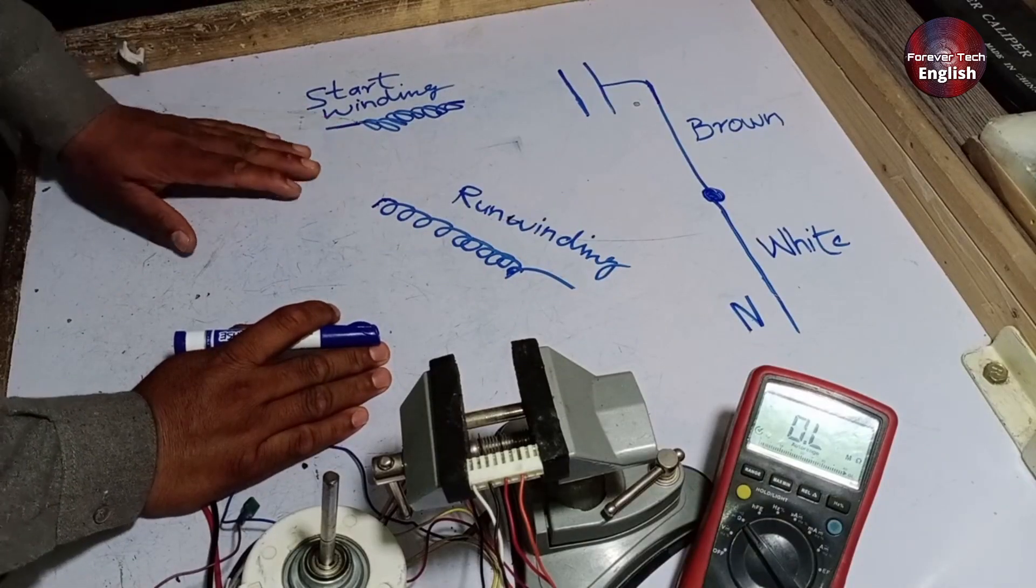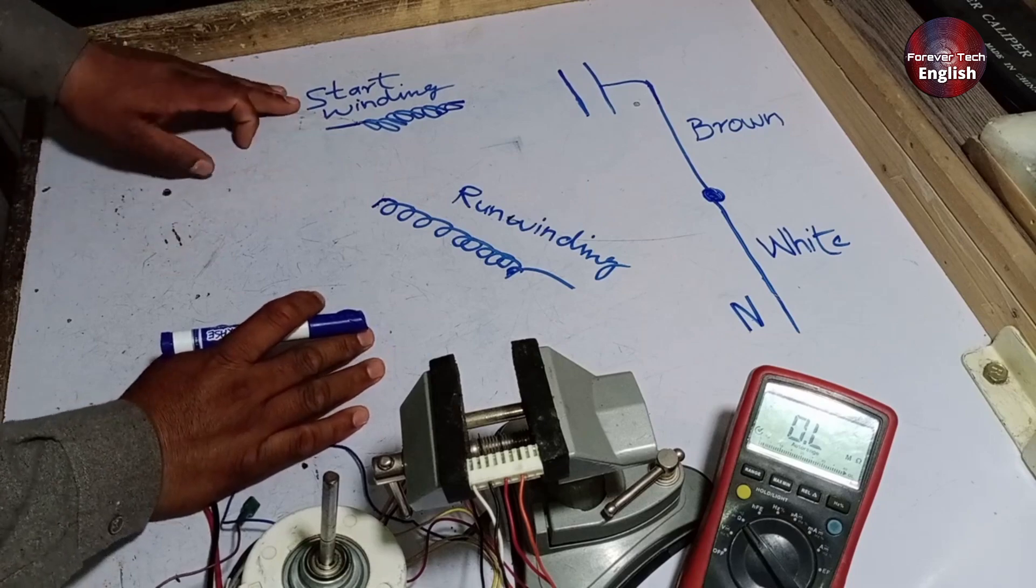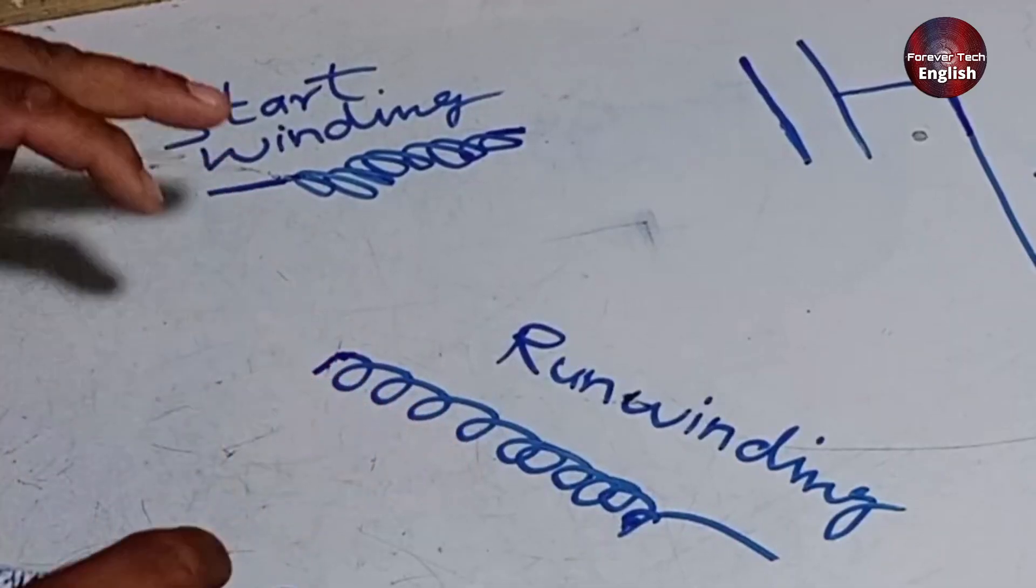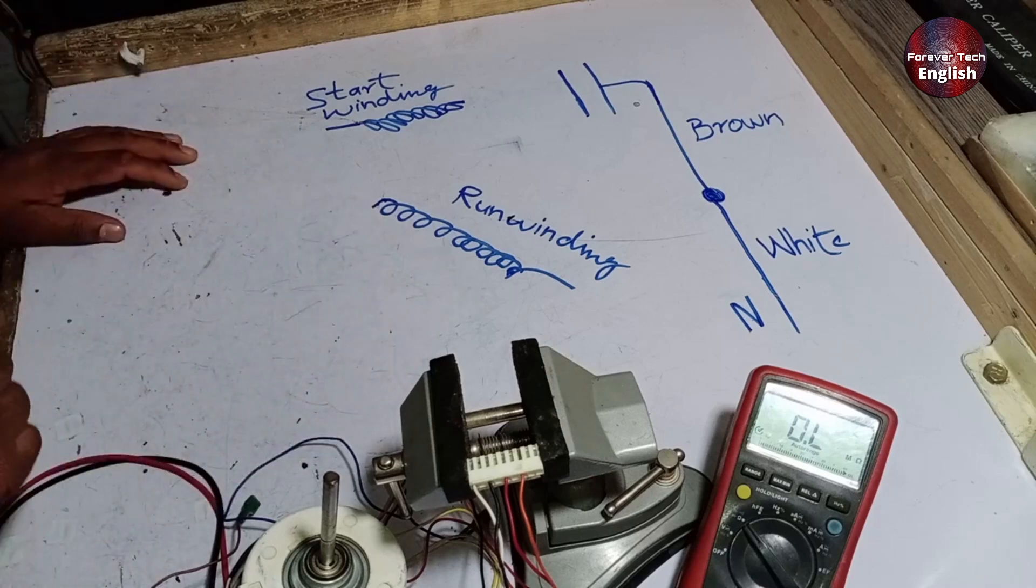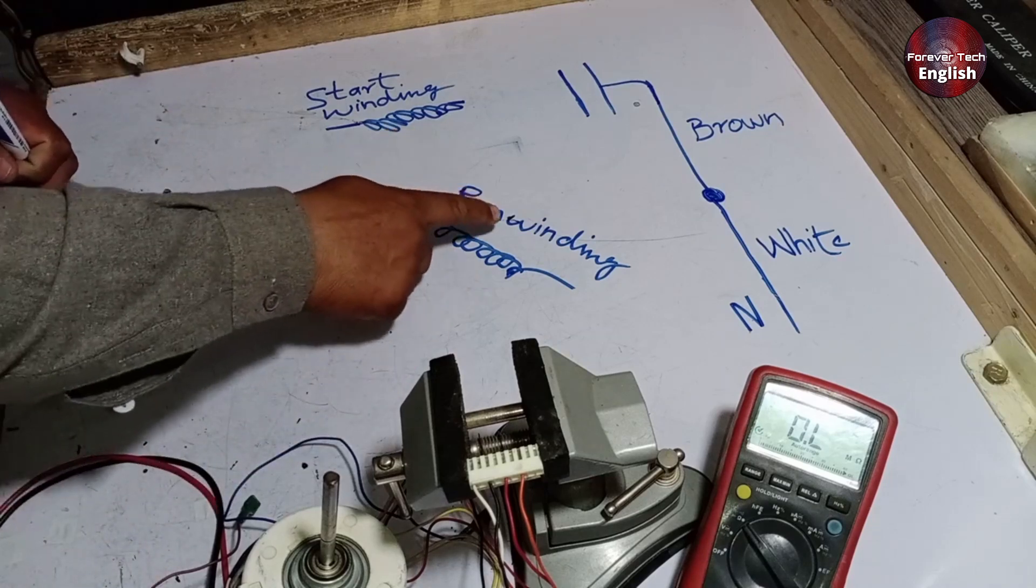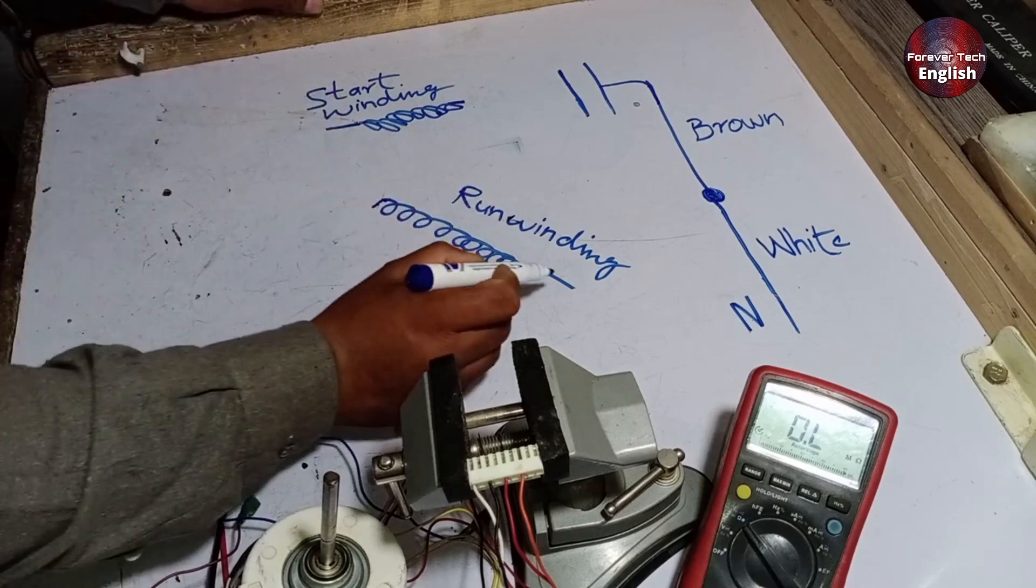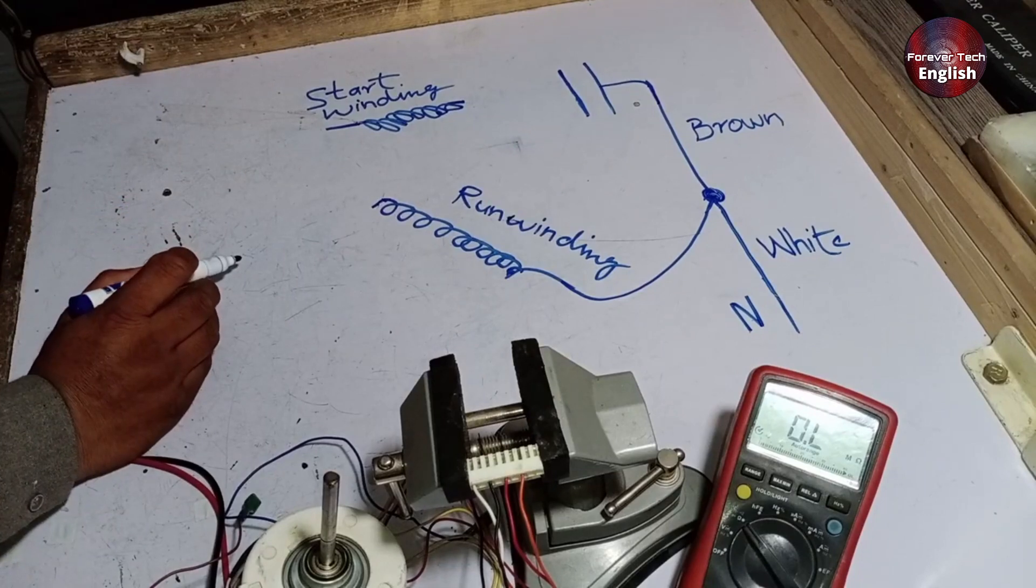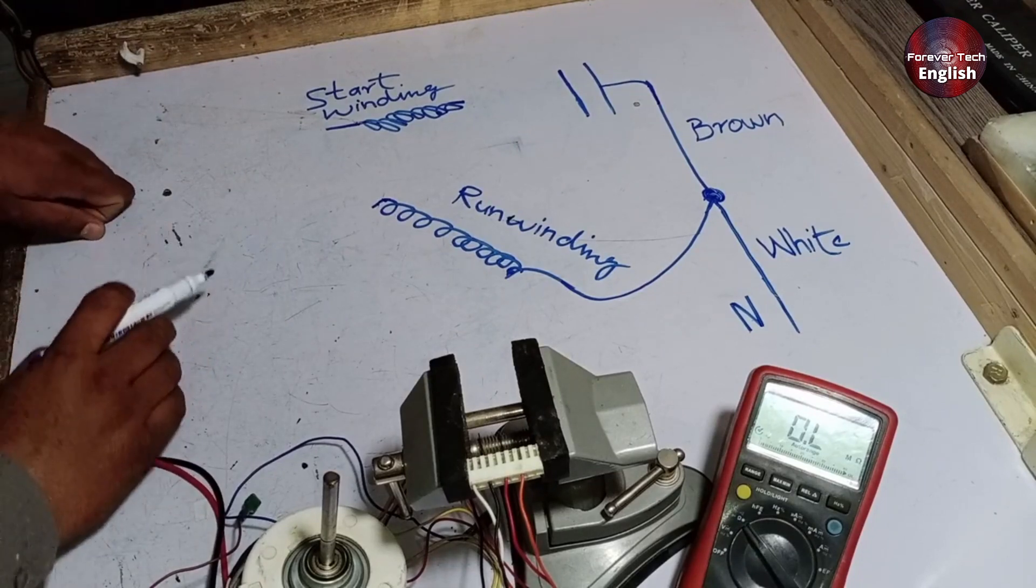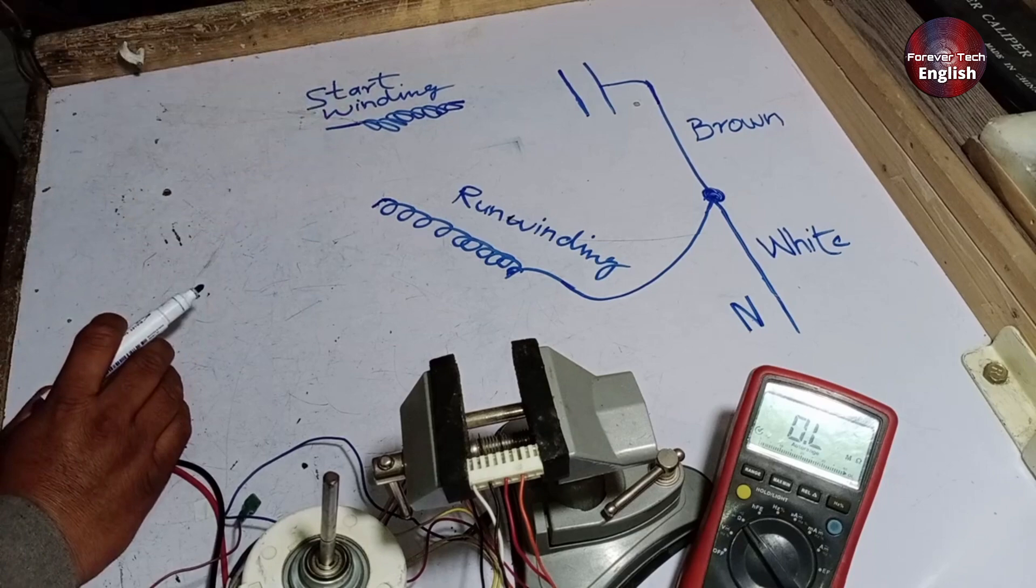We all know that when a motor is manufactured, it has both a starting winding and a running winding, and only then can it operate properly. Let's take a look at how to identify the connections among the six wires. First, when it comes to the running winding, one side of it will always be connected to the neutral. The first thing we need to find is the common point. To do that, we need to find the point with the lowest resistance value.